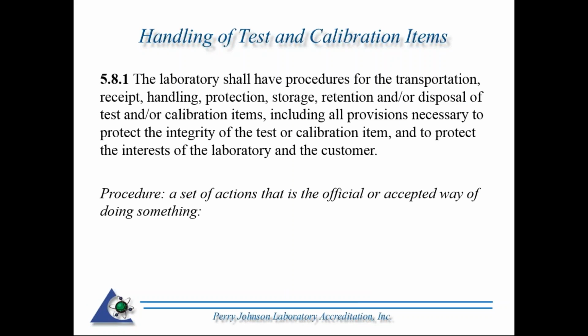Okay, so what we're going to do is look at each one of these clauses, and then dissect them in pieces. So 5.8.1 currently states the laboratory shall, and those of you that have joined us before know that when I say a shall, that's a must, that's a requirement. The laboratory shall have procedures for the transportation, receipt, handling, protection, storage, retention, and/or disposal of testing or calibration items, including all provisions necessary to protect the integrity of the test or calibration items and to protect the interest of the laboratory and the customers.